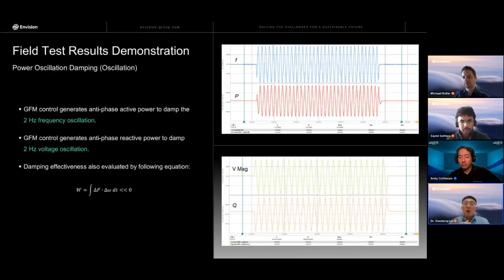This one is about the oscillation damping. We did both oscillation damping to frequency oscillation and oscillation damping to voltage oscillation. We did the test from 0.1 Hertz up to 3 Hertz, while the requirement is from 0.3 up to 2 Hertz. We also did the verification to make sure the active power or reactive power provided by our grid forming BESS is anti-phase. We also introduced an equation here to make sure we really provided the damping power.